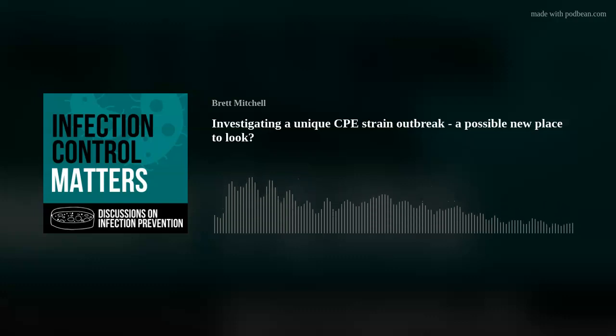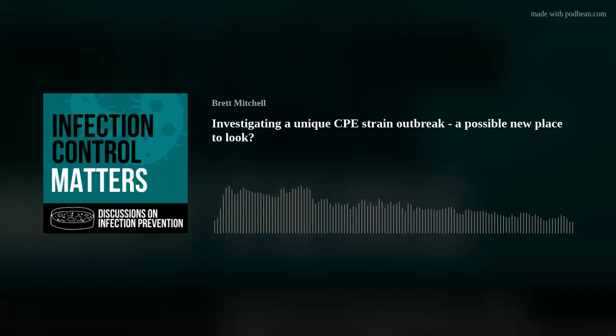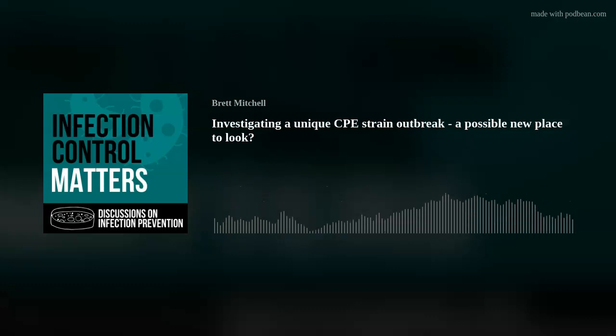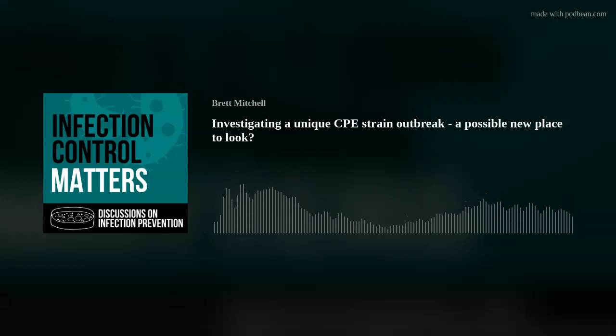So I think it's important to emphasise that we had machines from at least 3 different manufacturers, all of which had contamination to some degree. So it wasn't one particular manufacturer. The design issues were throughout. We did have some discussions with manufacturers. I don't think that was necessarily that productive. And going forward, we have also had discussions since with UKHSA about how we progress this as well.